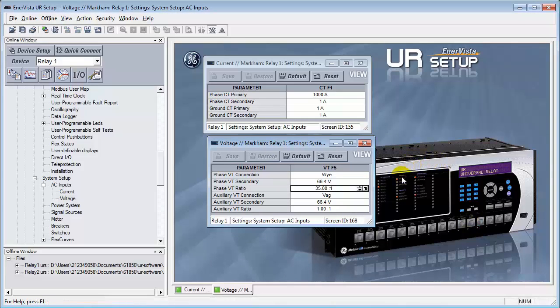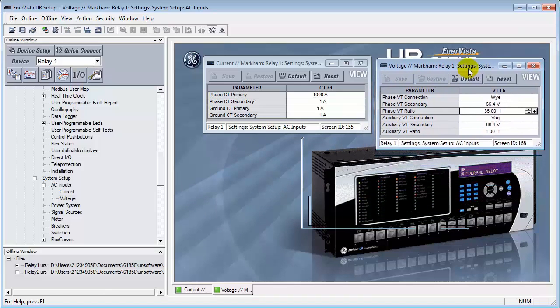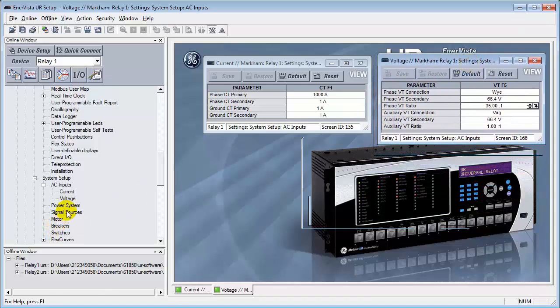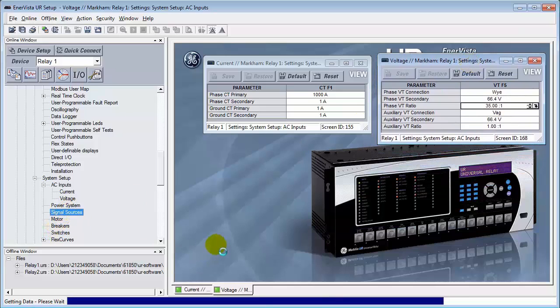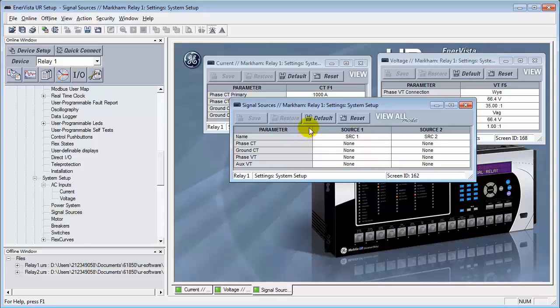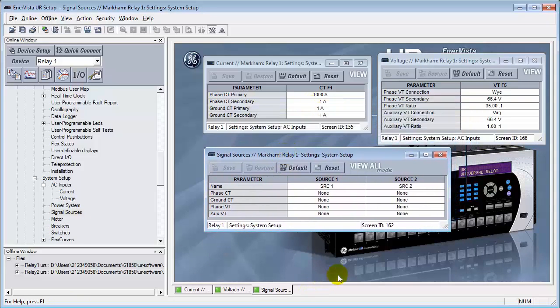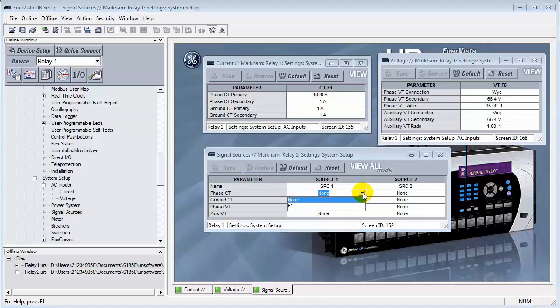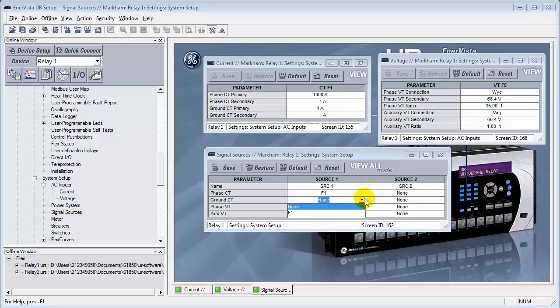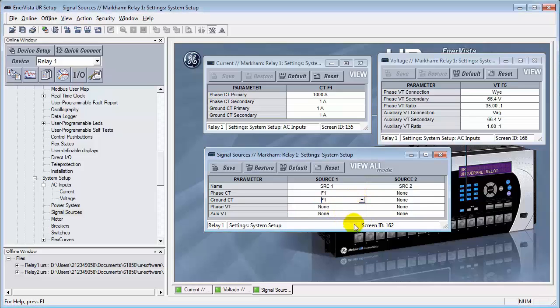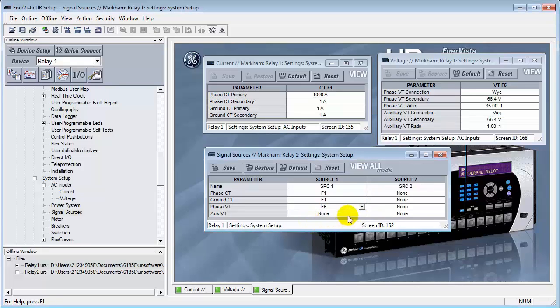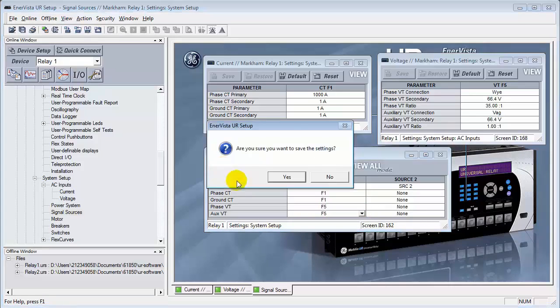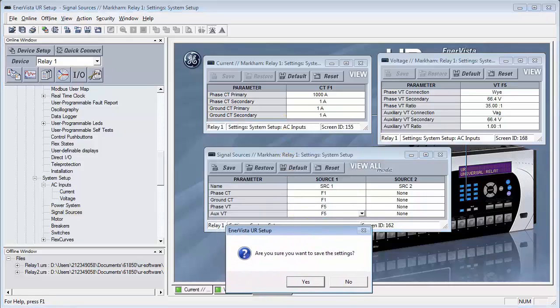Now, the most critical point of this is the last part, the signal sources. These need to be turned on. So, first of all, the phase CTs. We'll select our module that we're going to be expecting the current inputs from. And the phase VT voltage, which we click on the pulldown. This will be changed to F5. We will save those values.